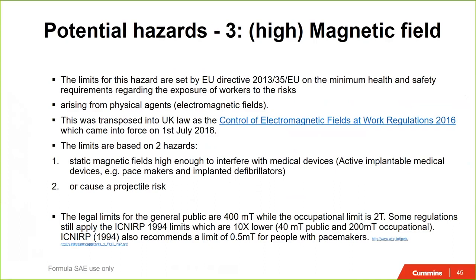It doesn't stop the device, doesn't damage the device. What it does is put it in program mode, which means that it won't deliver a shock should that shock be needed. I have a friend who has a pacemaker fitted, and she can't lean over a loudspeaker for a music system because that's enough of a magnetic field. What happens is the device vibrates inside her chest. Most people who have them implanted understand that that's what happens and know to move away. There's some data here on the limits, but just be aware, it's a relatively easy calculation to make.